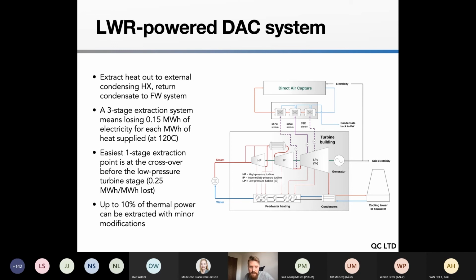If you only do 1 extraction, you might have to do that at a less optimal place, and the average temperature of extraction is higher, so you lose more megawatt hours per megawatt hour. A very strong limitation is, however, how much steam you can actually extract out of the system before you need to redesign it from the ground up. So can you go in, as Marcus was asking our previous speaker, and retrofit this solution into an existing plant, or do you need to make it ready for this from scratch? Our investigations show that up to about 10% of the thermal power of the plant can be extracted without any big problems. If you want to do more than that, you will probably need to make stronger modifications to the entire steam cycle.